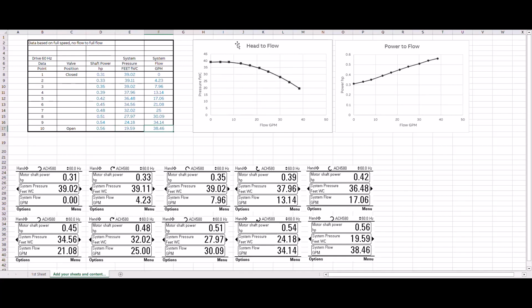So here we are. We've entered our data points in, and for our head to flow, with pressure in feet of water column up in the vertical and flow in the horizontal in gallons per minute, we can see a nice arcing curve that allows the drive to do calculations for head to flow. When we look at the power, which is the horsepower of the shaft of the motor, to the flow through the pump, we can see that we have a slope here. This slope allows the calculations for power to flow to be completed. This is all good information. This shows that this pump and motor combination will work for sensorless flow.